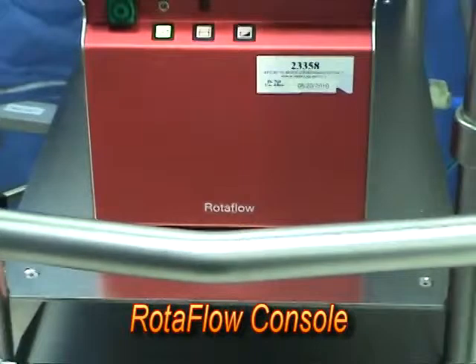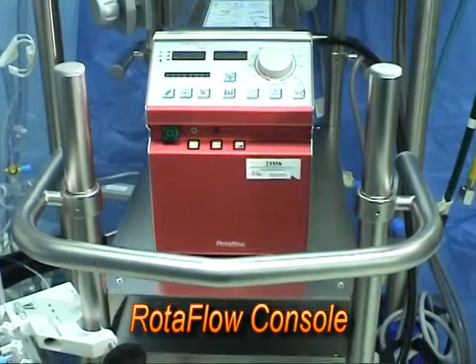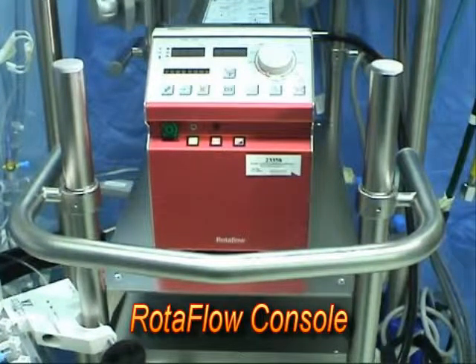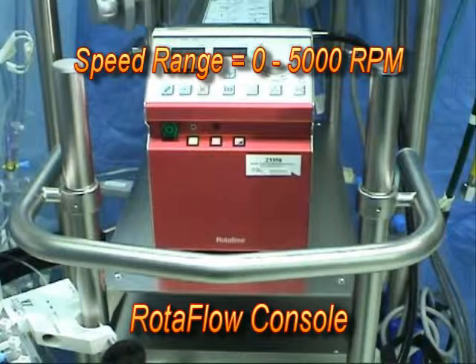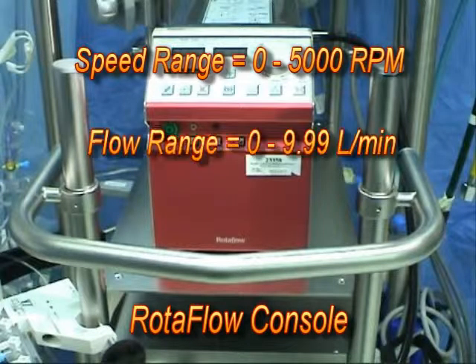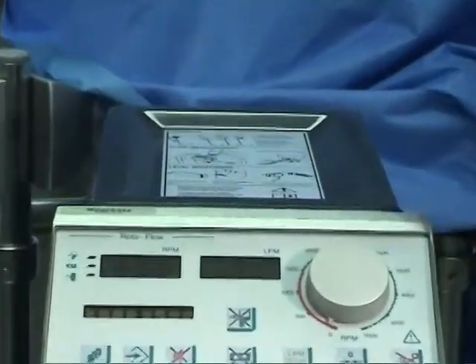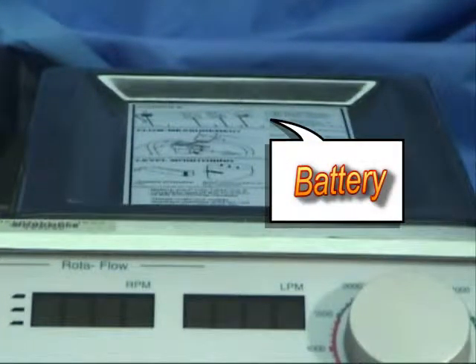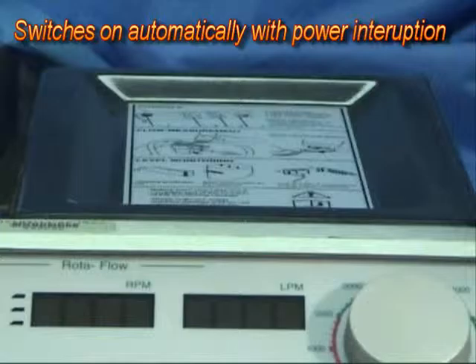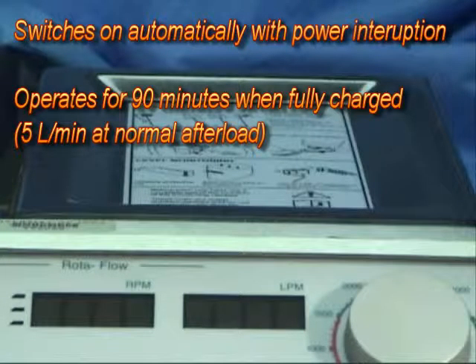The Rotaflow centrifugal pump system may be utilized either as a standalone unit or integrated into the Jostra HL20 console. It has a speed range of 0 to 5,000 RPM and a flow range of 0 to 9.99 liters per minute. From the front of the console, you can see the battery on top. The battery will switch on automatically if the power is interrupted and, if fully charged, will operate for 90 minutes at a flow rate of 5 liters per minute with a normal afterload.